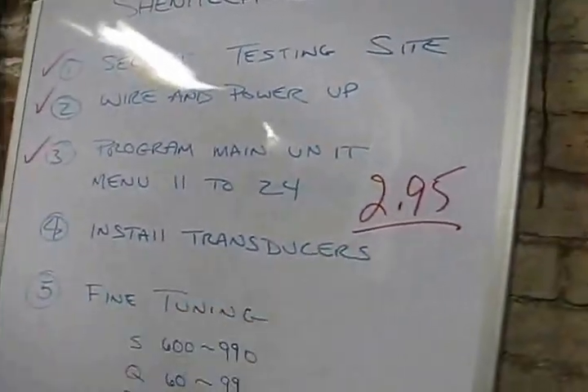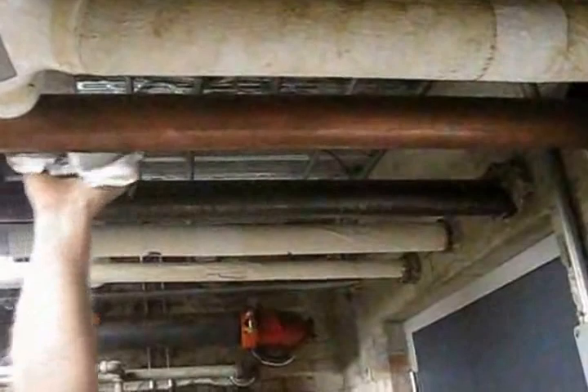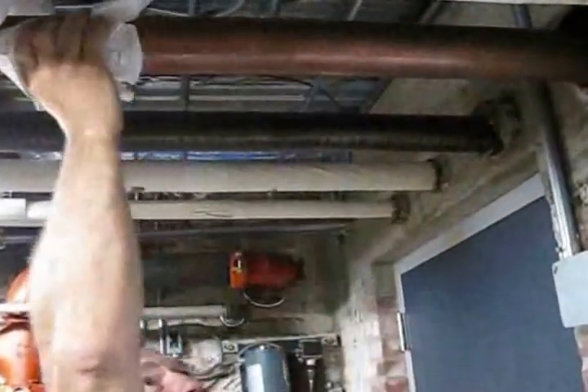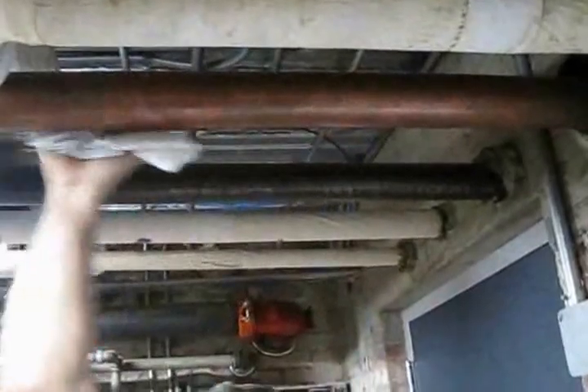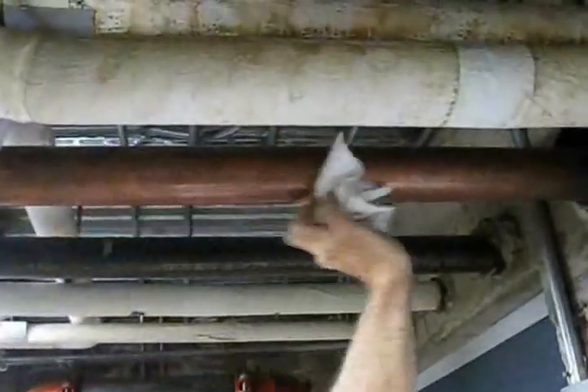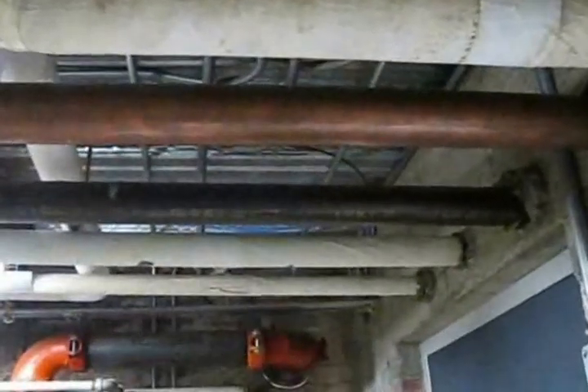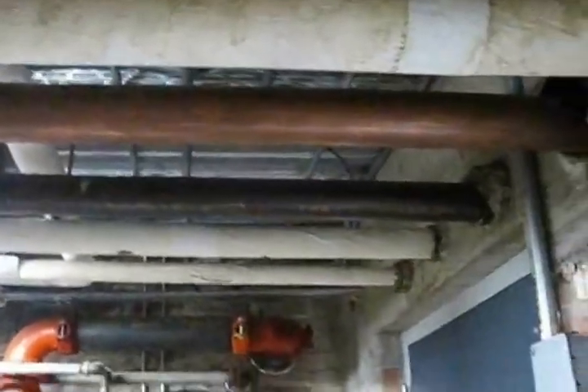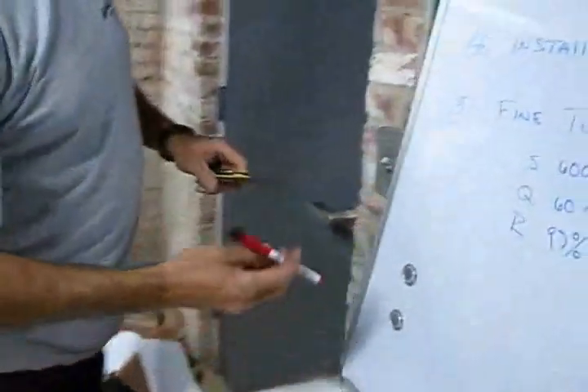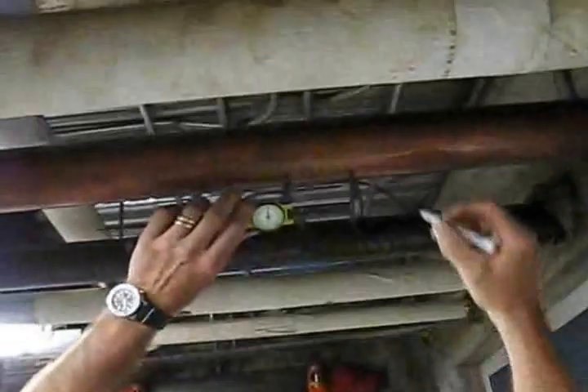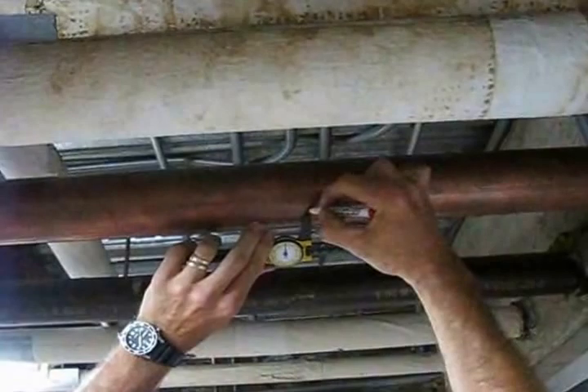Okay, now that we've programmed the main unit and we have our transducer spacing, which we recorded earlier, we go back to our pipe, which we exposed earlier in step 1, and basically we clean any residual material. If there's any rust, if there's any paint, we remove it at this time. It allows a clear reading for the transducers. We take the measurements we received earlier, we find our marks on the pipe, and we basically mark where our transducers will be placed using the number 2.95 we recorded earlier.